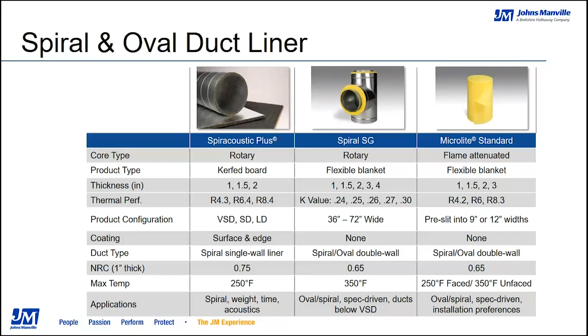The Spiracoustic Plus is a factory kerf cut product where you get a board that is consistently thick and provides R value all the way around that spiral inner circle. Great acoustical control and condensation control. It's really great for large diameter ducts, used in a lot of large stadium projects for bowl duct applications. We're talking 80-inch plus duct. It makes it a lot lighter weight, a really nice product for that.